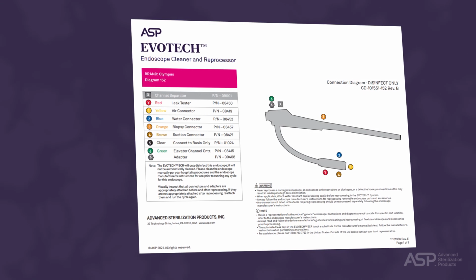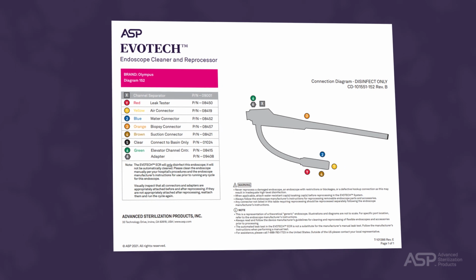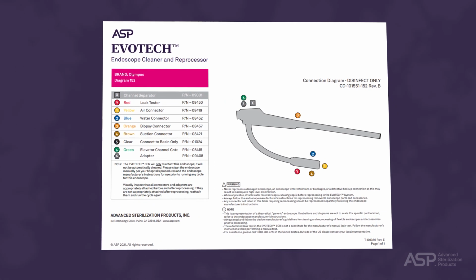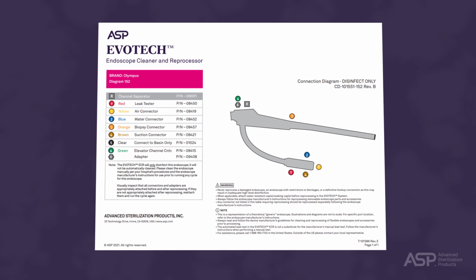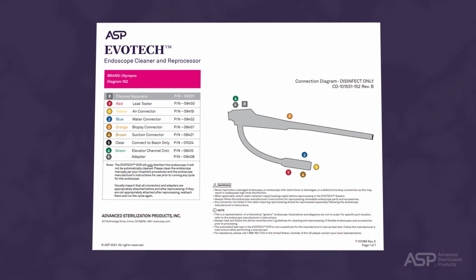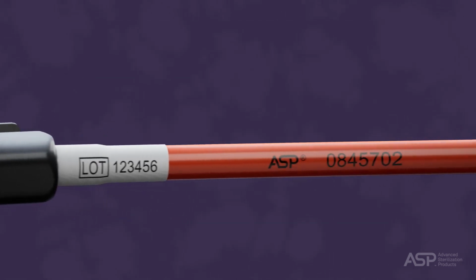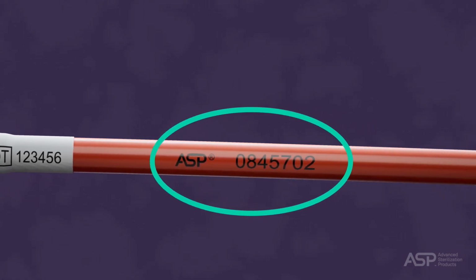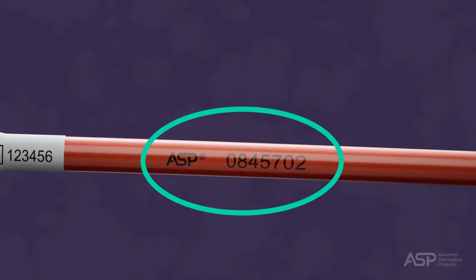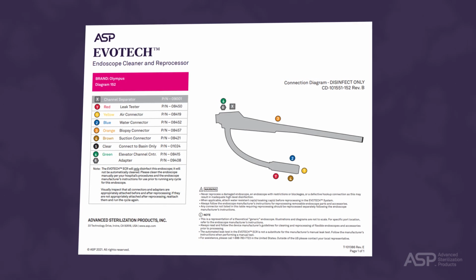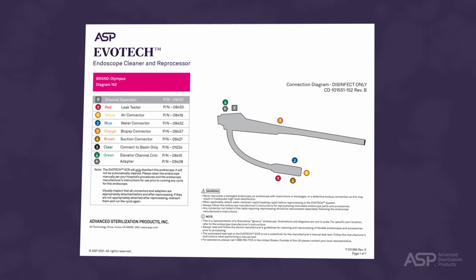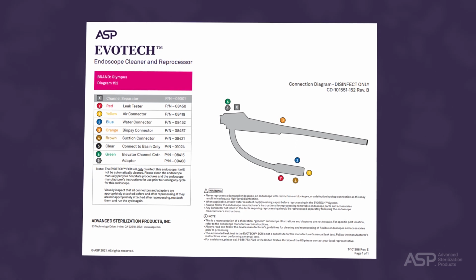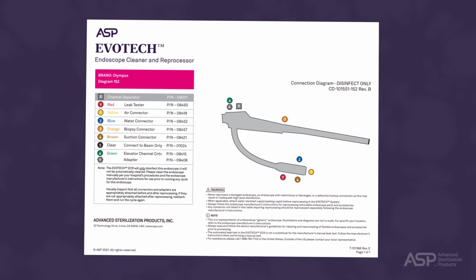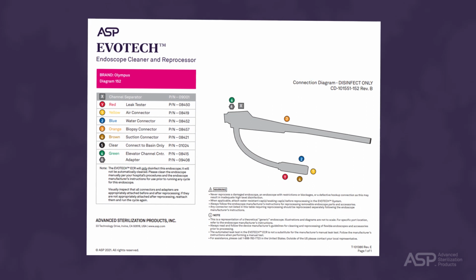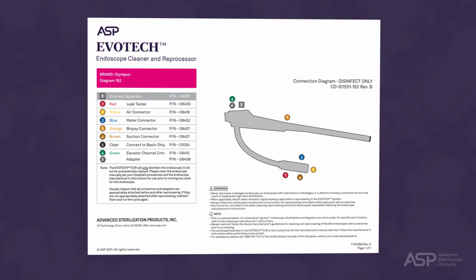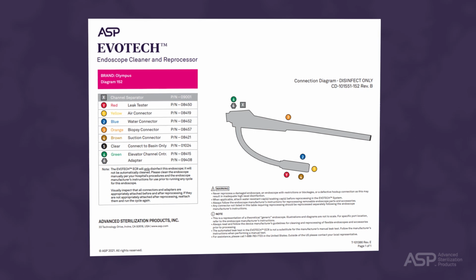Your account manager will supply you with connector diagrams after you provide an accurate list of endoscope models used in your facility. Connectors are identified by the first 5 digits of the connector part number. There are 7 digits on the actual connector. The last 2 digits reflect the revision number to be used when ordering parts. You can also reference your diagram number on the EVOTECH ECR screen. Make sure you confirm that the part numbers printed on the connectors are correct for the endoscopes you are processing. The diagram also demonstrates where to place your connector both on the basin and the endoscope.